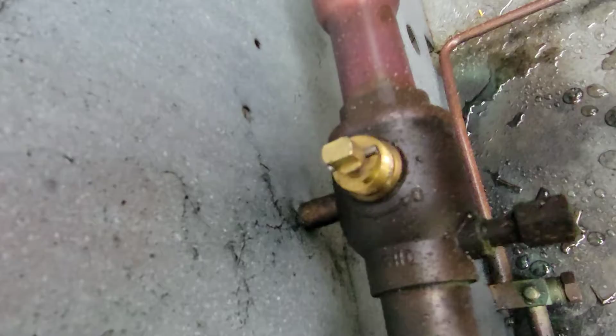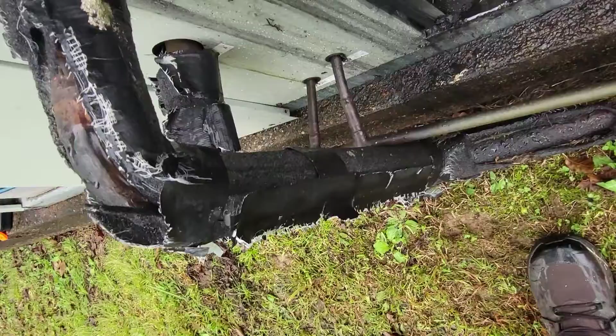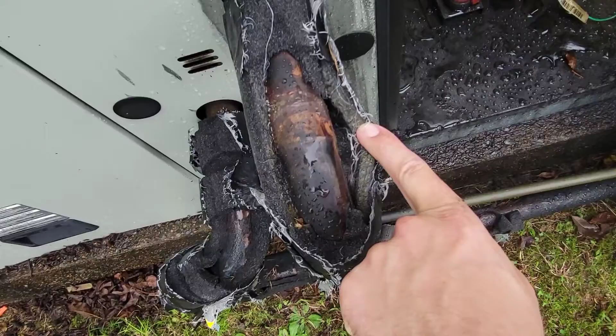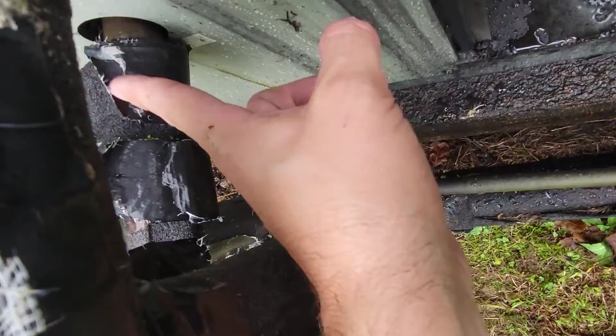What I did was close the valves, took these caps off here, and had to use an Allen wrench tool down there. This one right here, just a crescent wrench. I closed it off, and you can see you've got what looks like a 1/2 inch and at least a 1.25 inch line, and they're all going together. You see this section right here connects to the same line set.